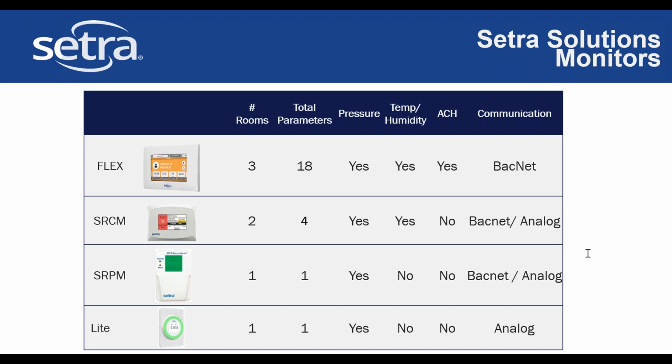We have another question by Al-Sayed Jaheen. Is there any module or monitor for the efficiency of HEPA filters or a VOC test? Typically for the VOC and the TVOCs, we do have the handheld particle counter that you can use for monitoring and taking the readings for the space you're interested in. And hopefully with the launch of the AQM, you would have continuous monitoring of the overall TVOCs. For monitoring the HEPA filters, usually the solutions are either a differential pressure switch mounted across the filter to give you an indication if it's clogged or not, or you can use a continuous differential pressure transducer to have a continuous reading of the pressure drop, which will indicate the amount of dirtiness or how clogged your filter is. This is typically the solutions that we see.